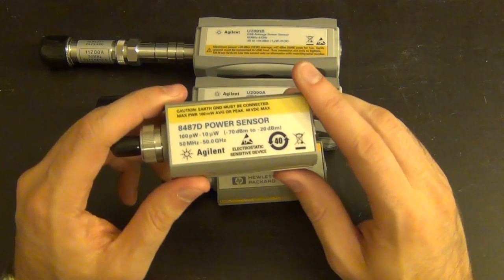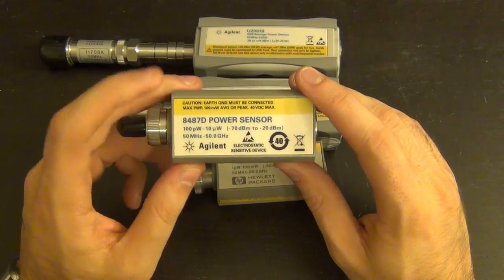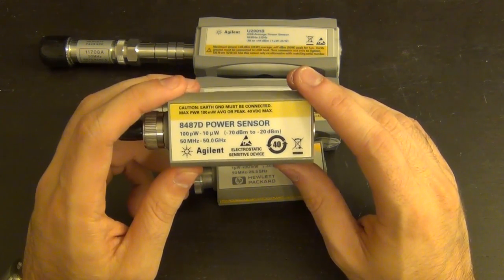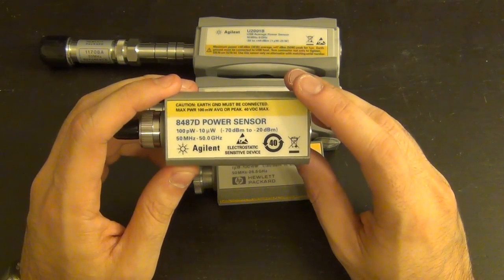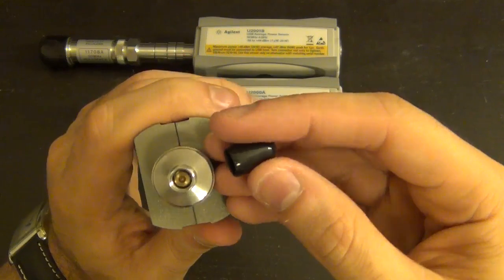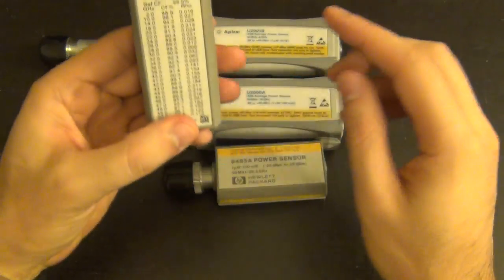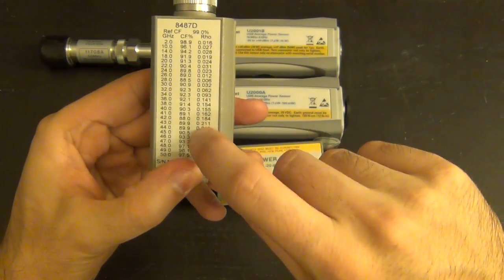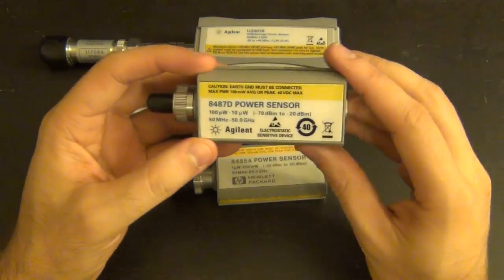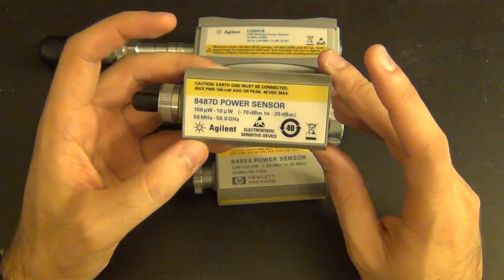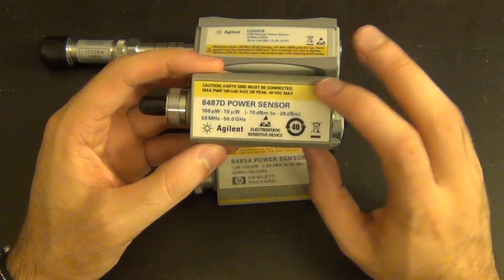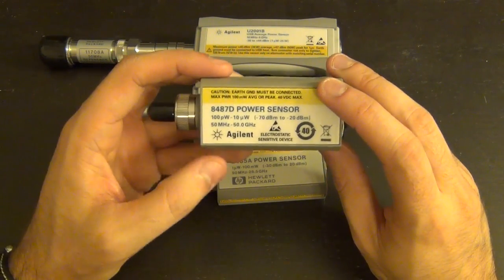Here's another one I have - my high frequency power sensor. It goes from 50 megahertz to 50 gigahertz, so it's a much higher frequency one, using a very high frequency V-type connector here. It also has a calibration table at the back. This is not an E-series one, so you have to type the table back in manually. This is an 8487D.